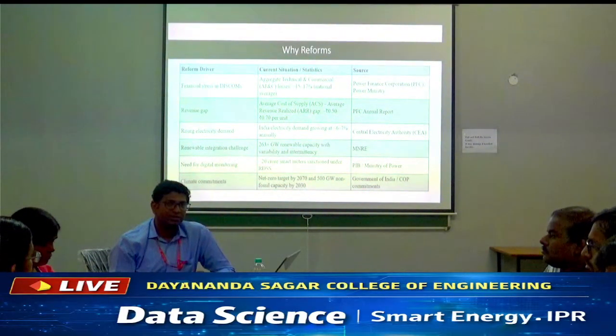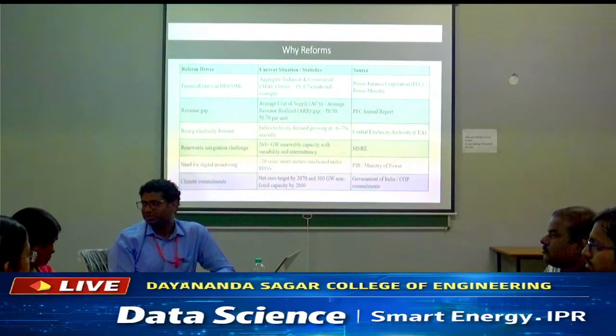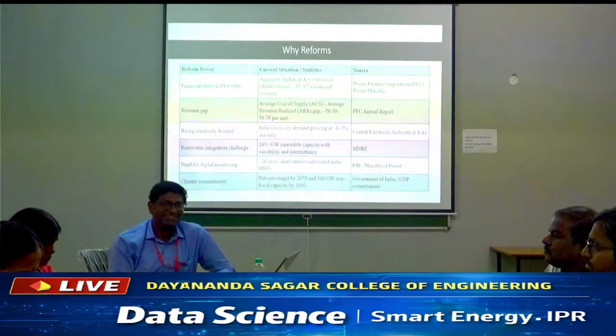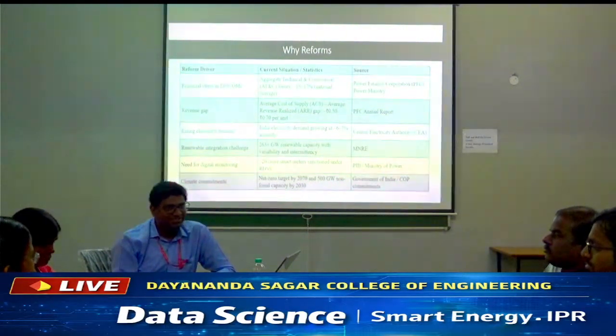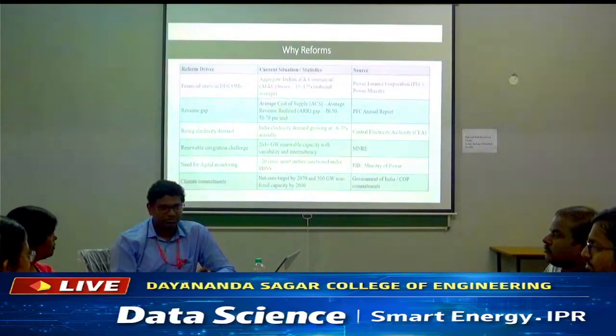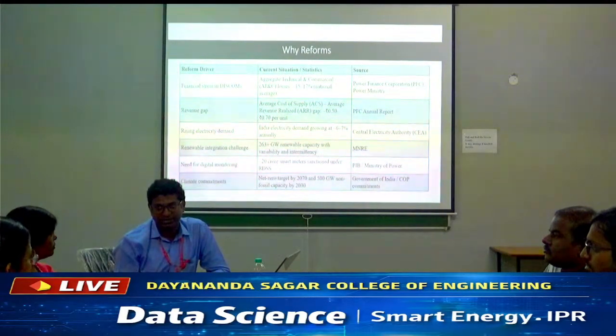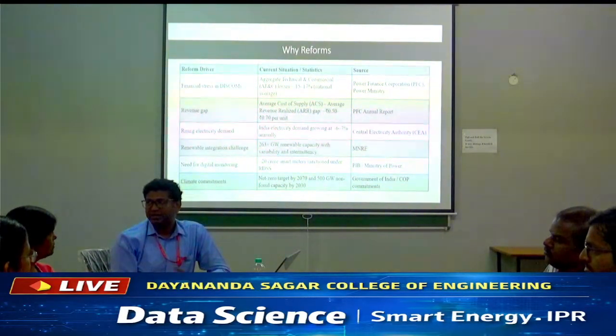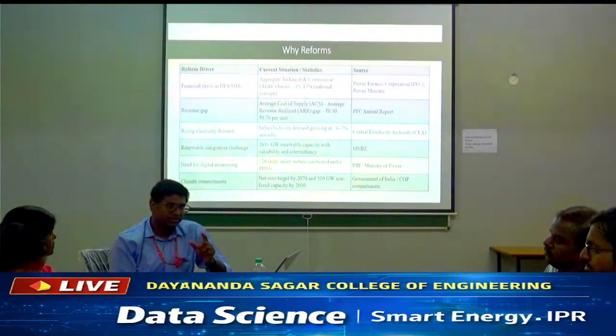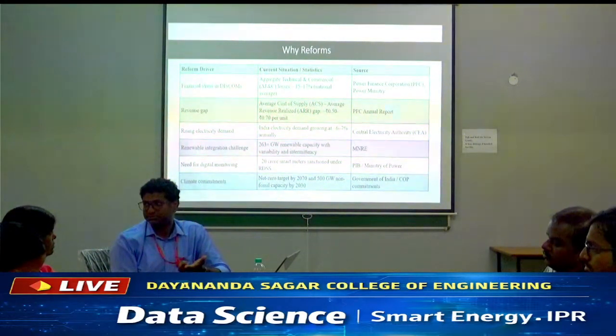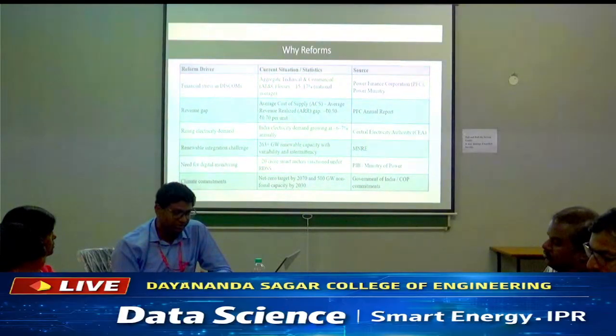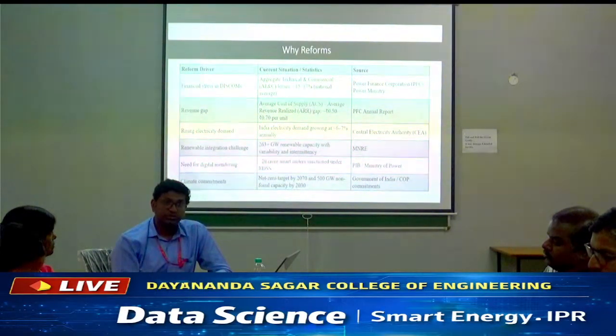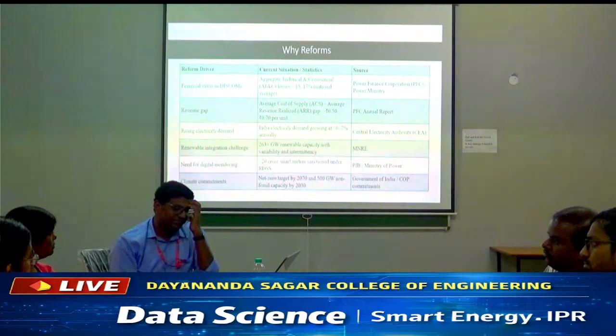We are not capable enough, because whatever power we generate through our rooftop power plant is single phase. Synchronizing single phase power with a 3-phase system, there is no technique at all. Something is there called a tri-vector meter, a device through which I artificially create one reference to inject the single phase power into a 3-phase system. That is there to inject, but that is not for every situation. What does every situation mean? That is another interesting story.